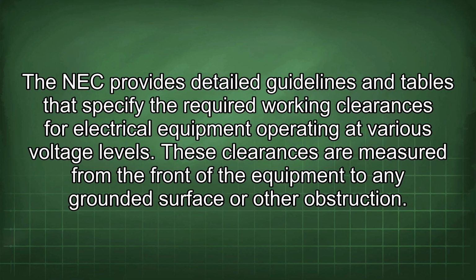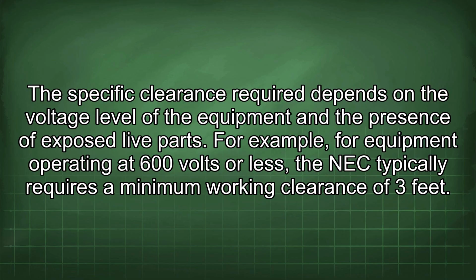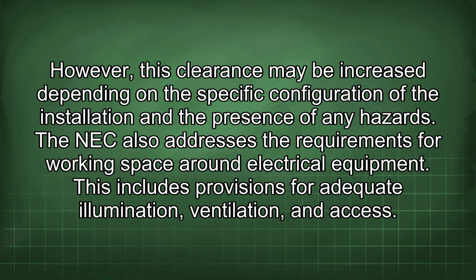The NEC provides detailed guidelines and tables that specify the required working clearances for electrical equipment operating at various voltage levels. These clearances are measured from the front of the equipment to any grounded surface or other obstruction. The specific clearance required depends on the voltage level of the equipment and the presence of exposed live parts. For example, for equipment operating at 600 volts or less, the NEC typically requires a minimum working clearance of 3 feet. However, this clearance may be increased depending on the specific configuration of the installation and the presence of any hazards.